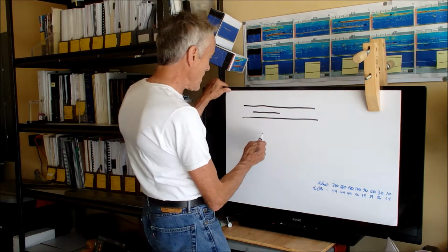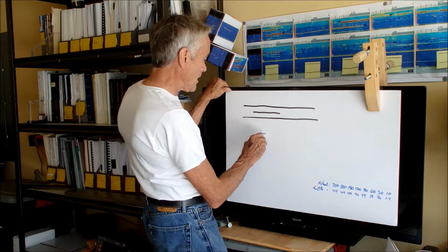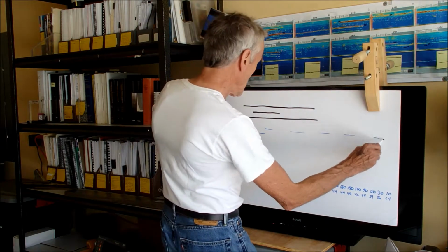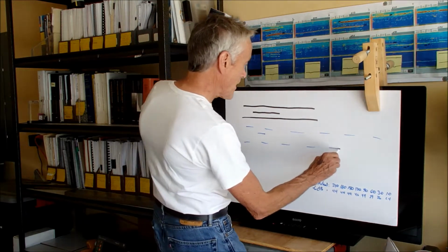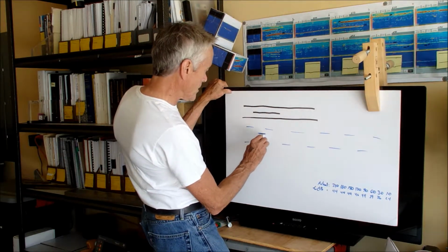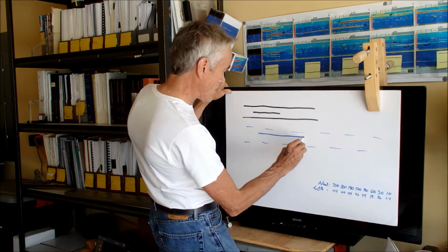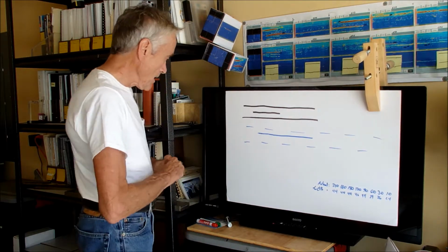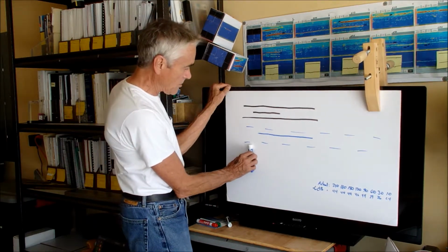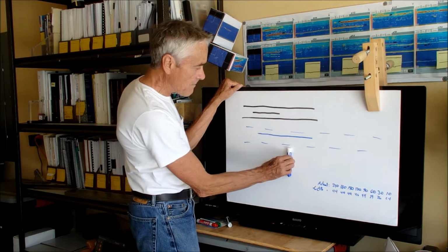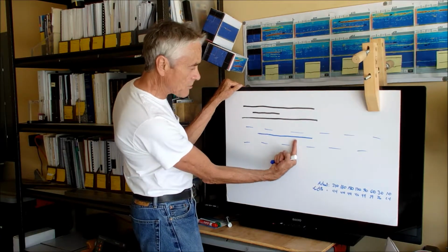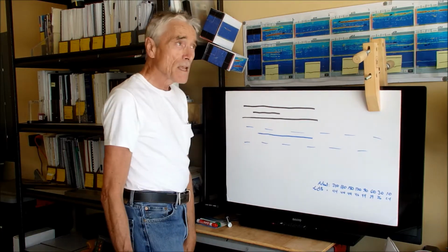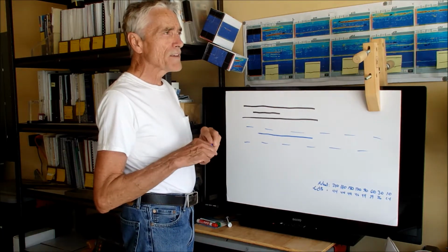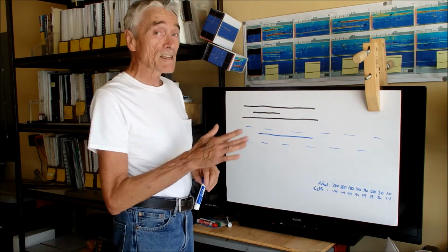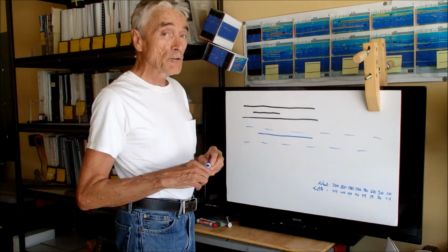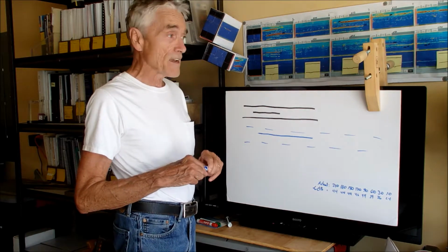Let's say you had a weld, and inside that weld you had a large indication with some length to it. You know, if this was your angle beam transducer and you got into the middle of the flaw with your angle beam transducer shooting sound into the flaw, as long as the flaw had the same reflectivity along its entire length, then you could do 6 dB drop flaw length sizing.